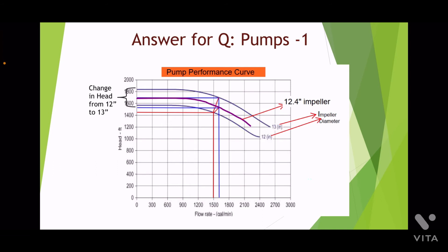Either we can calculate the new impeller diameter required based on the new rated flow and then find the head developed, or for the new flow rate we can first calculate the new head required based on the discharge system and then based on this new calculated head find the impeller diameter and then find the operating point. If you do it the latter way, then we end up with a 12.4-inch impeller size rather than a 13-inch impeller size.